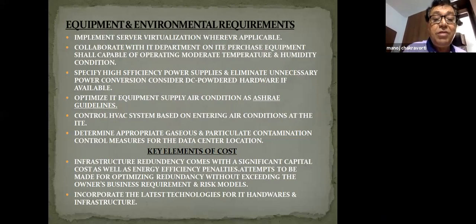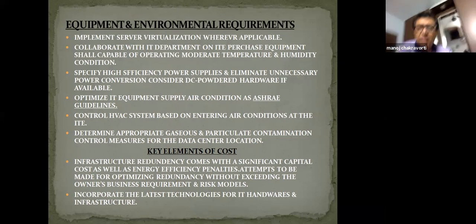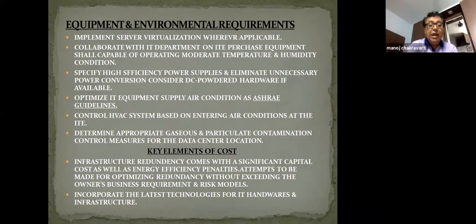Next is the control of the HVAC system, which is basically the entire air conditioning at the inlet and different things. Basically, in a server, what happens? In a server you have a lot of sensible heat. When your racks are on, you have a lot of heat. Naturally, you are dealing with sensible heat. But all the racks are not operating all the time. So there should be good control of the load, and accordingly the air conditioning system also should operate.